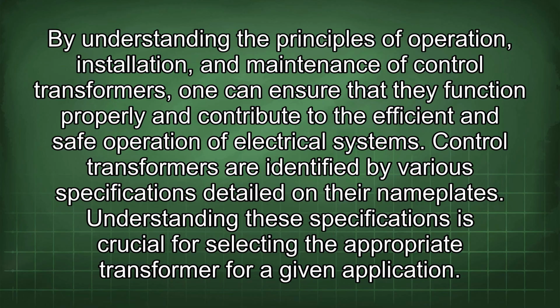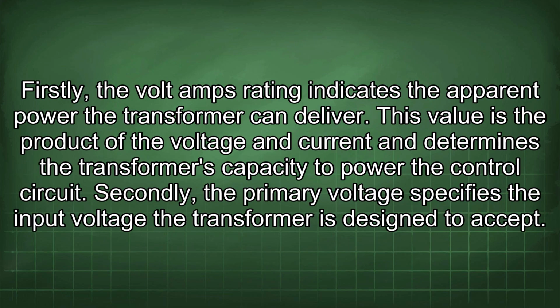Control transformers are identified by various specifications detailed on their nameplates. Understanding these specifications is crucial for selecting the appropriate transformer for a given application. Firstly, the volt-amps rating indicates the apparent power the transformer can deliver. This value is the product of the voltage and current and determines the transformer's capacity to power the control circuit.